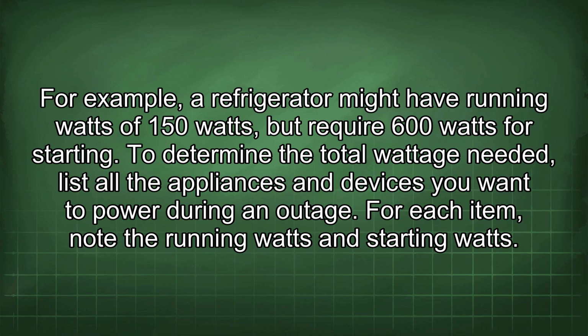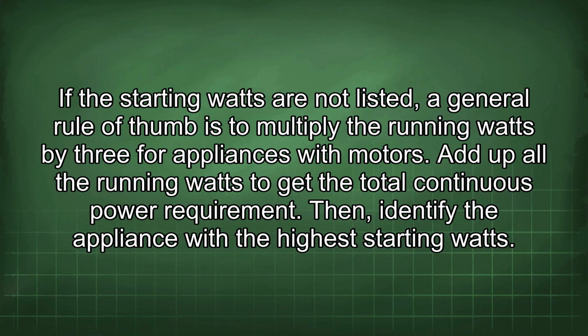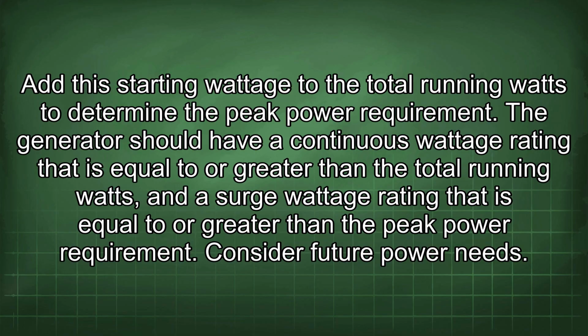To determine the total wattage needed, list all the appliances and devices you want to power during an outage. For each item, note the running watts and starting watts. If the starting watts are not listed, a general rule of thumb is to multiply the running watts by 3 for appliances with motors. Add up all the running watts to get the total continuous power requirement. Then, identify the appliance with the highest starting watts. Add this starting wattage to the total running watts to determine the peak power requirement.